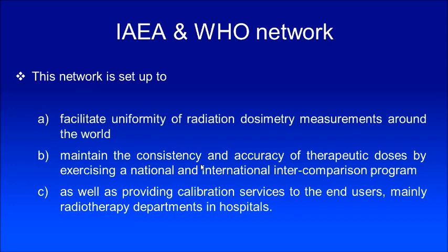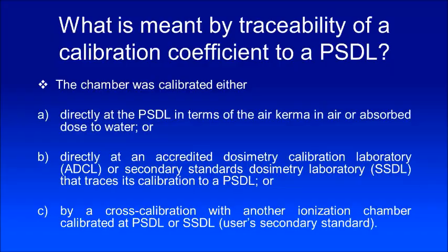They bring in all the primary standard and secondary standard laboratories and several user clinics into the network, maintaining consistency and accuracy of therapeutic doses by exercising a national and international intercomparison program. Earlier they were using TLD for this — they called it a TLD audit. Now they use glass dosimeters, called an RPLD audit. They also provide calibration services to end users. If your country does not have a secondary standard dosimetry laboratory, you can approach the IAEA for calibration of your dosimeter.